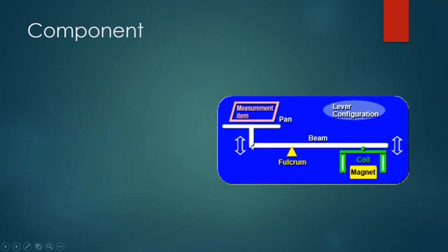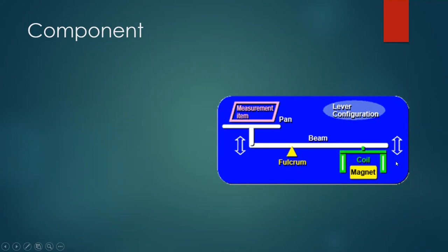The mechanism: a fulcrum supports a beam connected to the pan where the item to be measured is placed. On the other end of the beam, there is a coil, a magnet, and an electromagnet, which increases or decreases the counterpoise weight based on the current passing through it. The weight on the pan determines the current generated. When the current applied becomes equal to the load, the beam is level and the reading is taken.